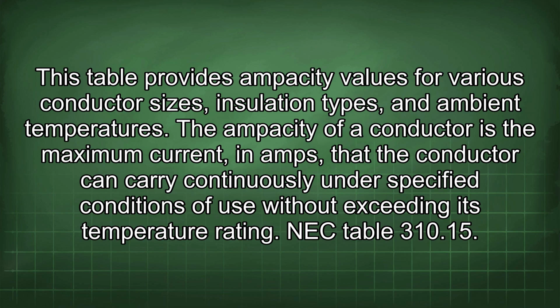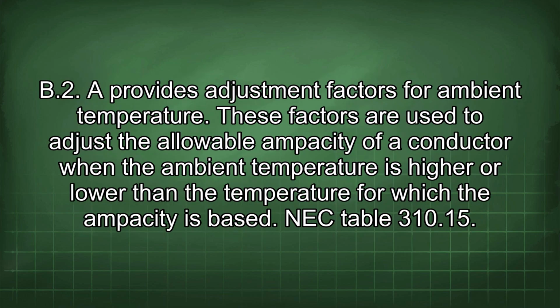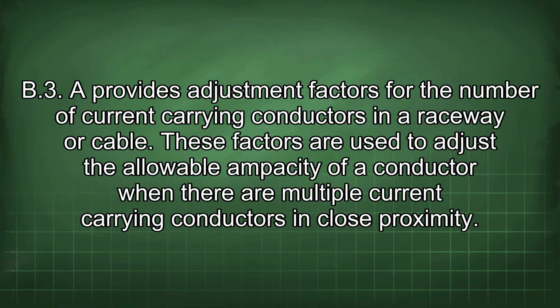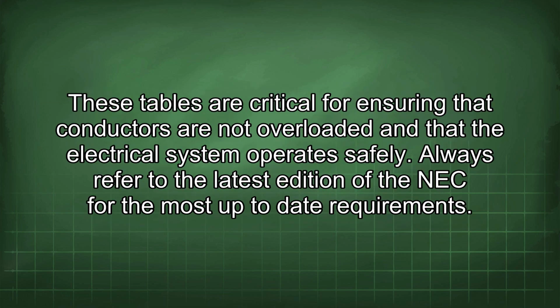NEC Table 310.15(B)(2)(a) provides adjustment factors for ambient temperature. These factors are used to adjust the allowable ampacity of a conductor when the ambient temperature is higher or lower than the temperature for which the ampacity is based. NEC Table 310.15(B)(3)(a) provides adjustment factors for the number of current carrying conductors in a raceway or cable. These factors are used to adjust the allowable ampacity of a conductor when there are multiple current carrying conductors in close proximity. These tables are critical for ensuring that conductors are not overloaded and that the electrical system operates safely. Always refer to the latest edition of the NEC for the most up-to-date requirements.